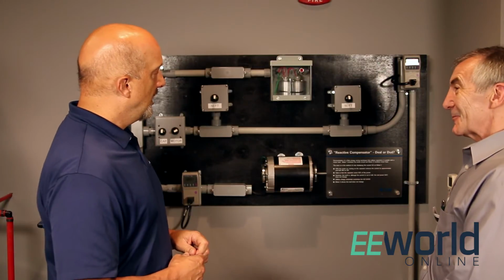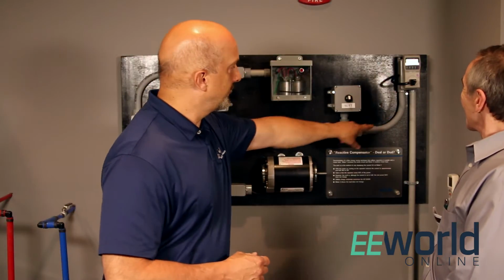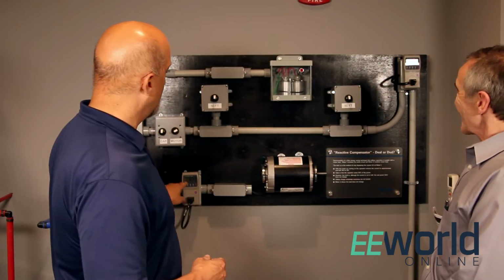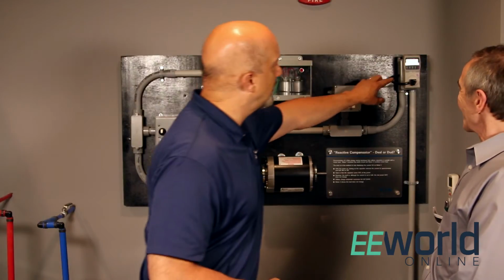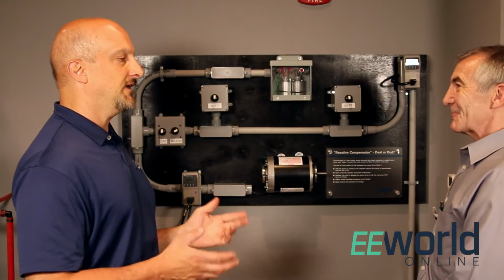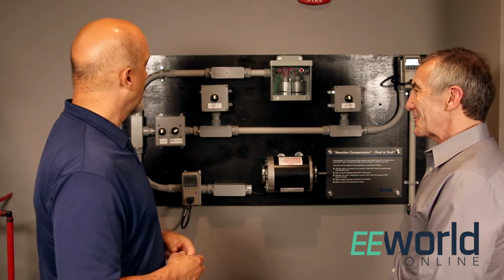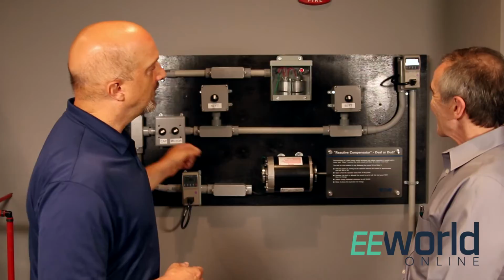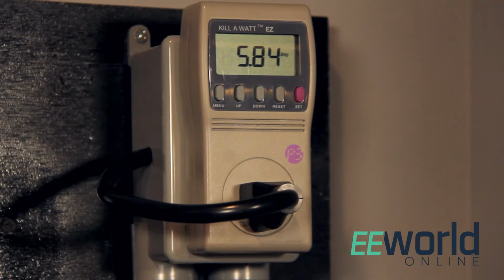So what we have here is 120 volts coming in supplying power to the motor. Now what they'll do is take a meter like this and show the actual amps, not the watts, going to the motor. Then when they turn on the capacitor, they'll focus you on the amps again, and say, in our case, it went from almost 6 amps to about 3 amps. So they cut the current in half.